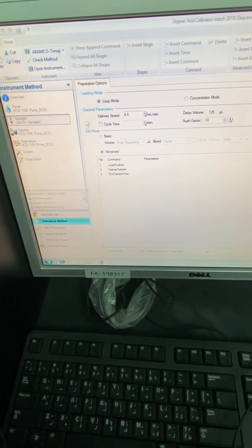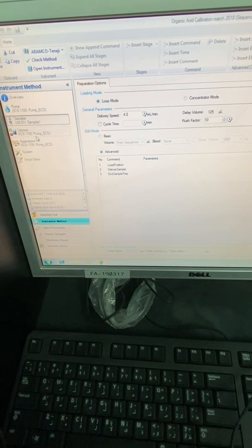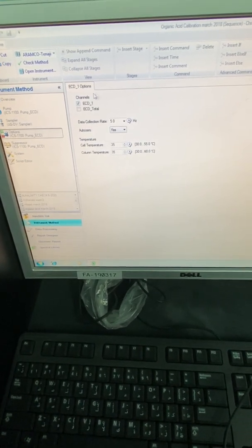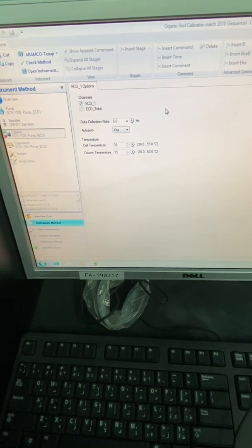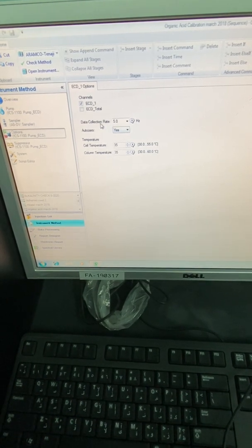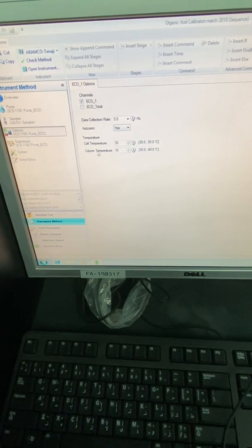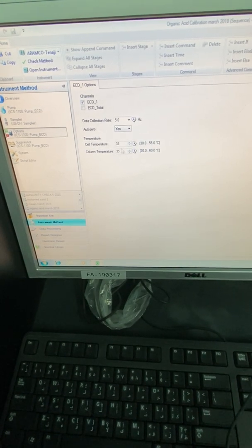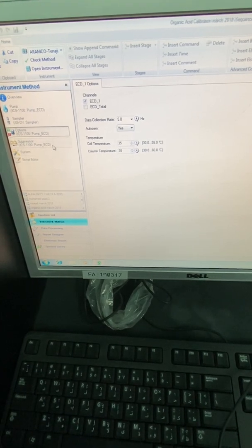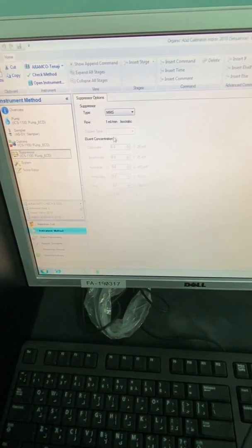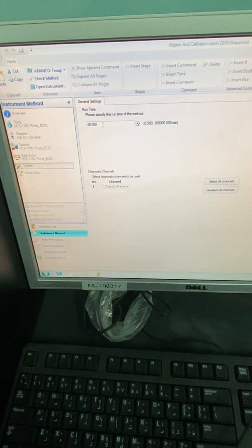The sampler, if you are using the auto sampler, you will put the information of the sampler here. The pump, how many channels you want to see. The ECD for the conductivity detector and the data collection rate. The temperature of the column here you have to mention, how much temperature you want your column to be. All of this from either the column or the bulletin you are using. The suppressor, the type of the suppressor you have to mention based on each application.